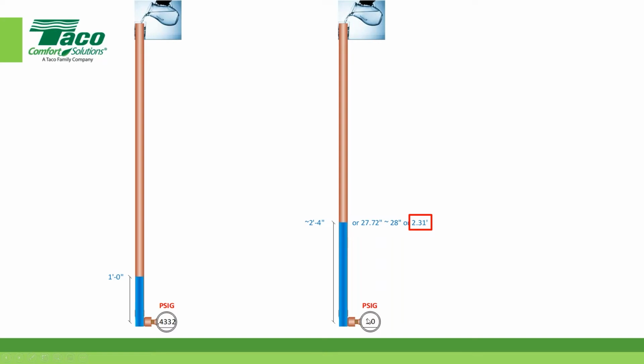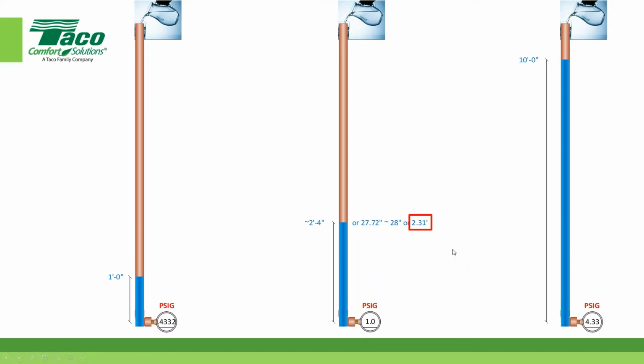Okay, if we want to figure what psi is, based on feet of head, I take the feet divided by 2.31. And the other way around, if I have psi and I want to figure out what feet of head it is, it is just whatever psi I have times 2.31. That's why you'll see that in some of these equations, and you've got to be familiar with that. Okay, and it's linear too. Notice 0.4332, or 4.33 at a 10-foot height. So just think of this analogy when you're looking at that left-hand column of a circulator performance curve.